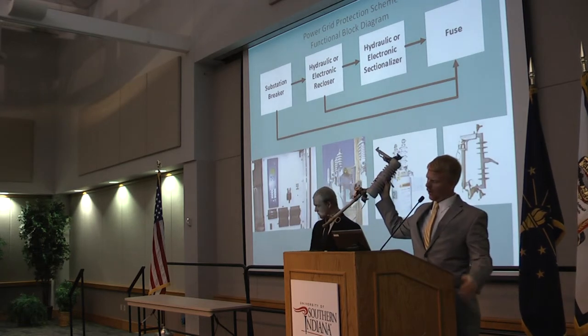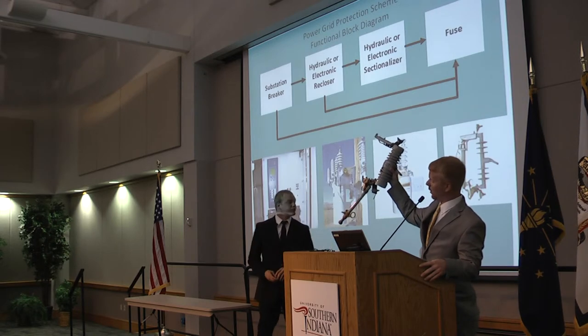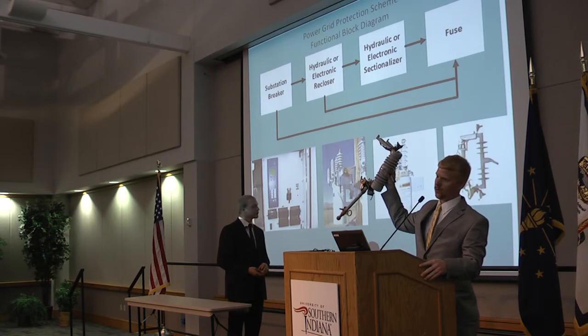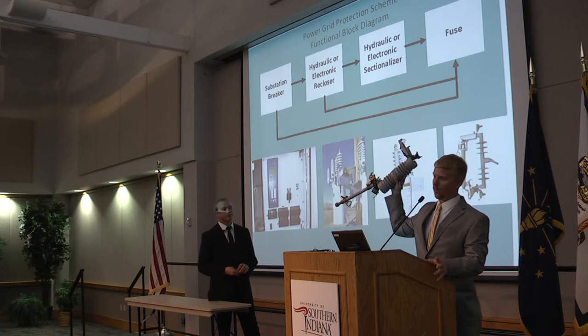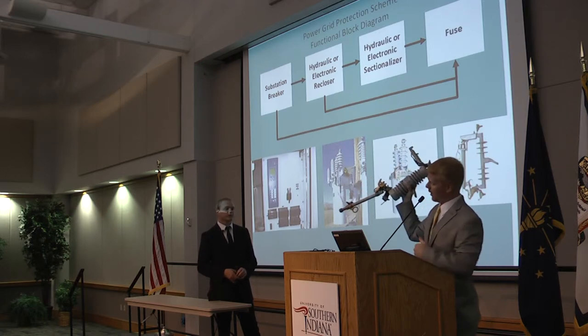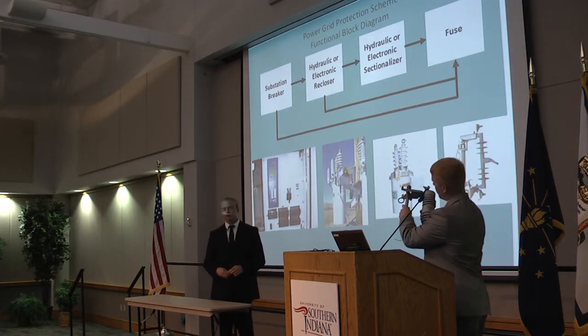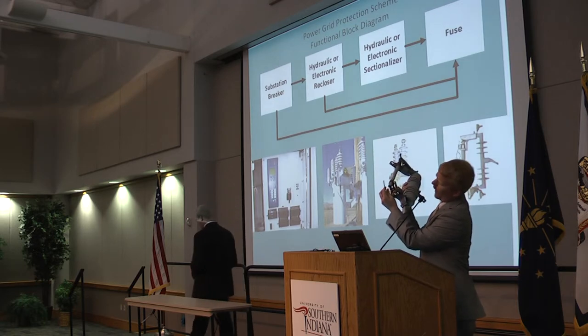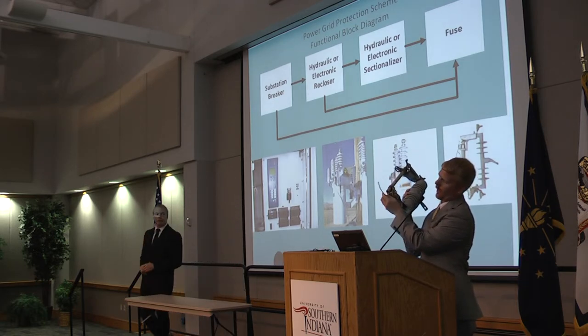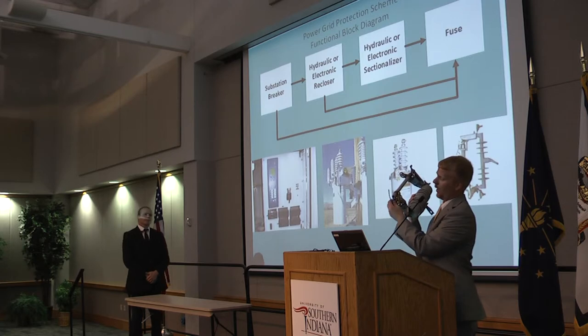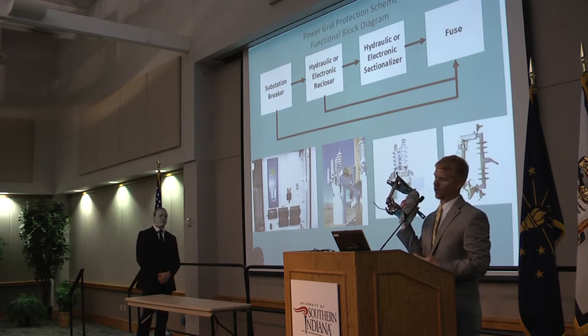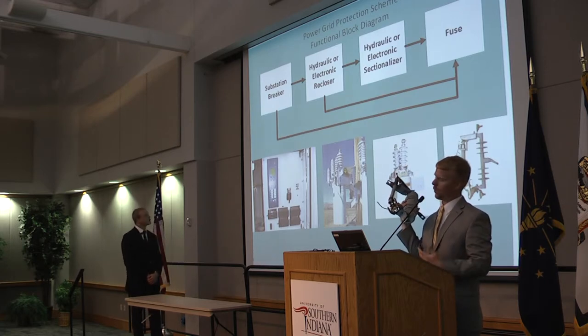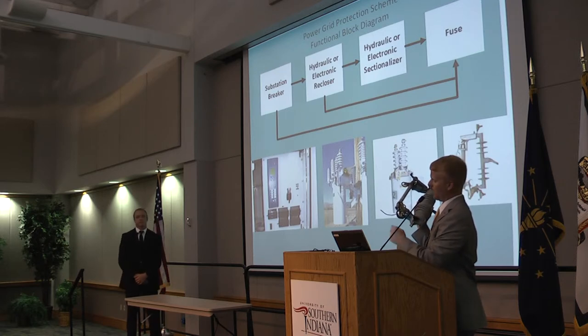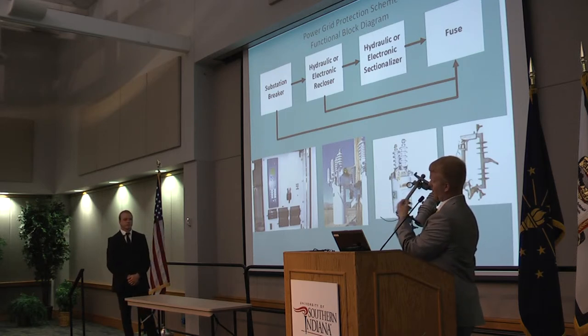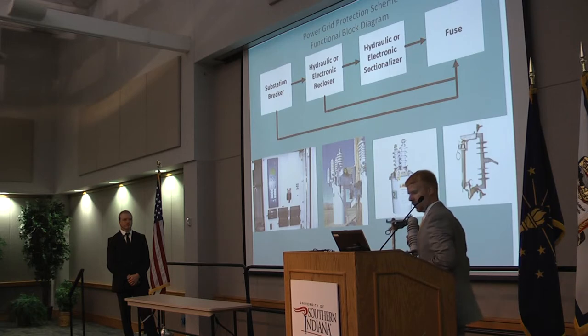So when you're standing out as a lineman, you can look up, and if you see this, then you know that the fuse is blown, and that's how we know that we have an outage in the area. The fuse itself is this little wire, and this is rated for different amperages, and that is decided by the engineer on what size fuse we need at each point based on the load downstream. This wire will melt, and like I said, it's a chemical reaction that causes the explosion.